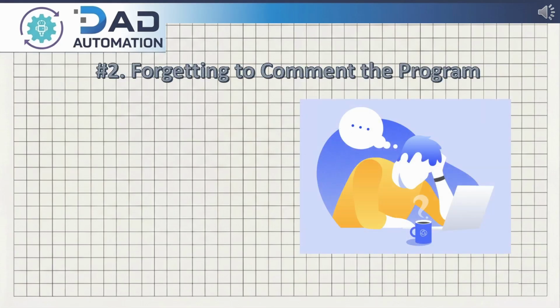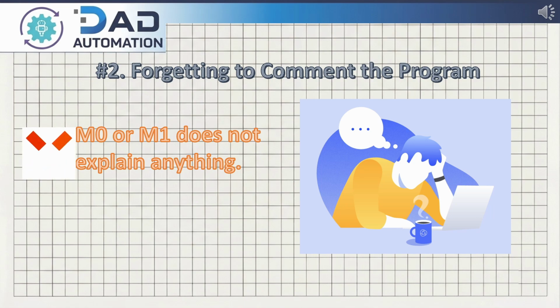Another very common mistake in PLC programming is forgetting to comment your program. When you are writing logic, everything may seem clear at that moment. But after a few days, or when another engineer looks at your program, it becomes very difficult to understand what each rung is doing. For example, a simple coil like M0 or M1 does not explain anything. Instead, always add comments such as motor start command, conveyor running status, or alarm reset condition. Good comments help you quickly understand the purpose of each section of code. They also make troubleshooting much faster during machine faults.